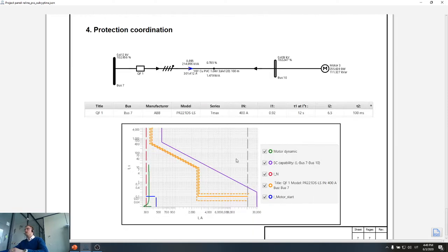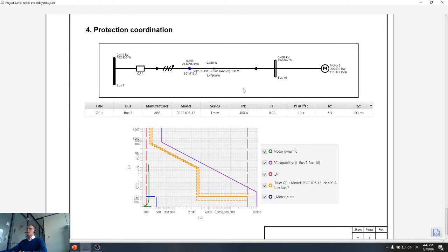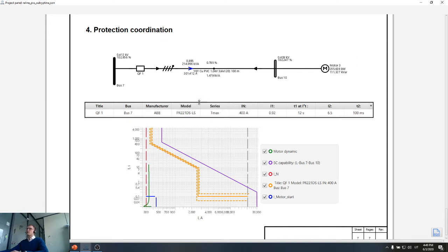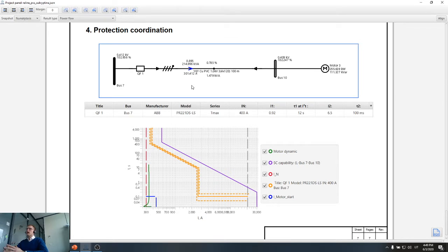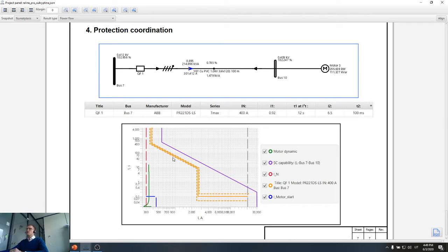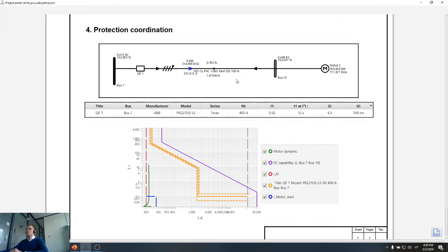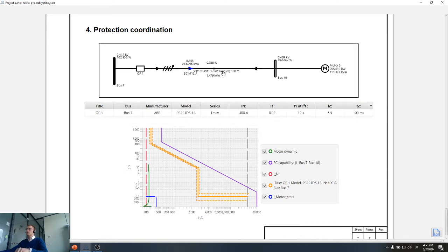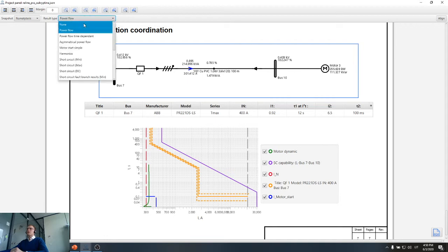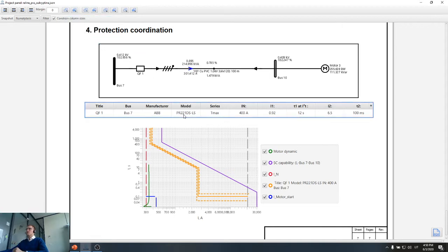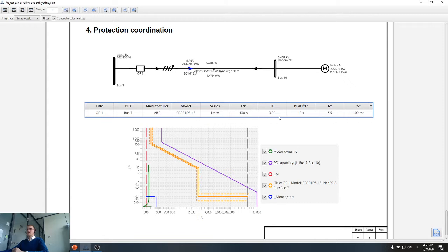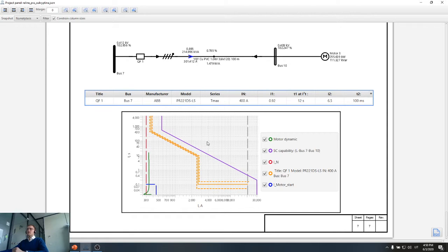Later on, you can provide information about the single line diagram. The most common way to provide information regarding the protection coordination settings is to provide part of the single line diagram with the considered breaker or the relay, then to provide settings of the breaker and also a TCC curve of the breaker. So again, in software you can do this kind of thing automatically. Like you can add the single line diagram. You can specify what kind of results should be represented on the single line diagram. It can be short circuit currents. It can be power flow results. Then you can add the breaker itself. So this is the data about the breaker, and then you can add basically a single TCC curve of the breaker.